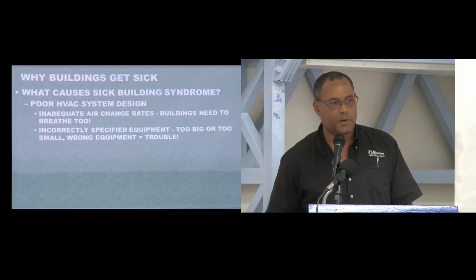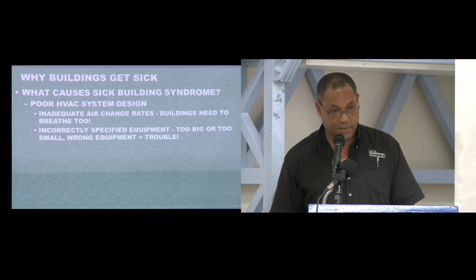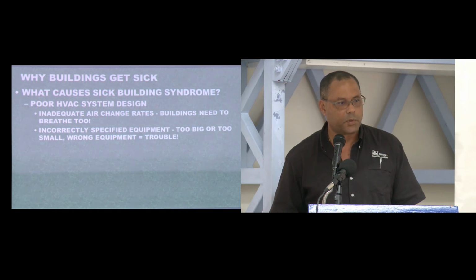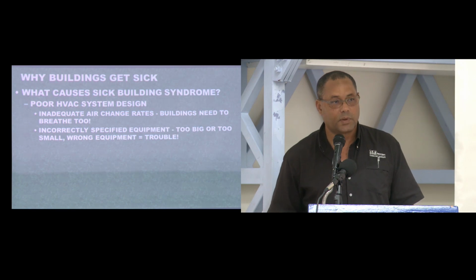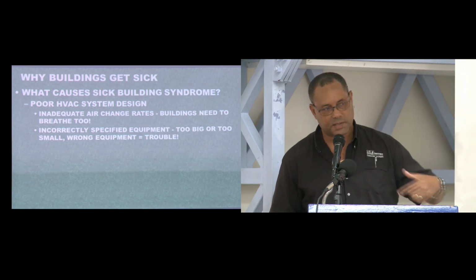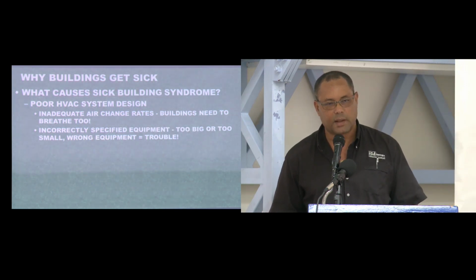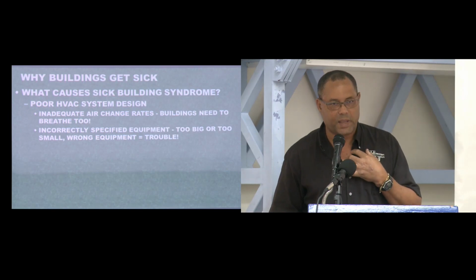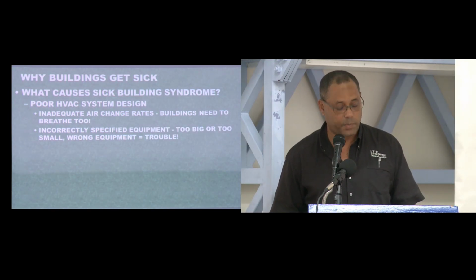So how you set up your ventilation system has a key impact on your comfort cooling and what your conditions are going to be. Too big or too small when you're specifying your equipment: if it's too small, obviously nobody's going to be comfortable. Everybody's going to complain about being hot and sweaty. People will be disgruntled. If it's too big, you can have overcooling, so people are too cold. Another problem that results from overcooling or your system being too big is that it shuts down the cooling very quickly. Your air is still circulating, but it's not actually actively cooling the air. So the moisture stays in the air. So you get cold, wet air circulating, people feel uncomfortable, it gets clammy, and it's a perfect environment for the growth of mold and other pathogens.